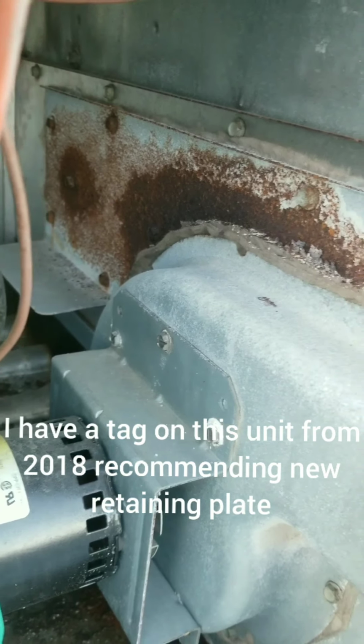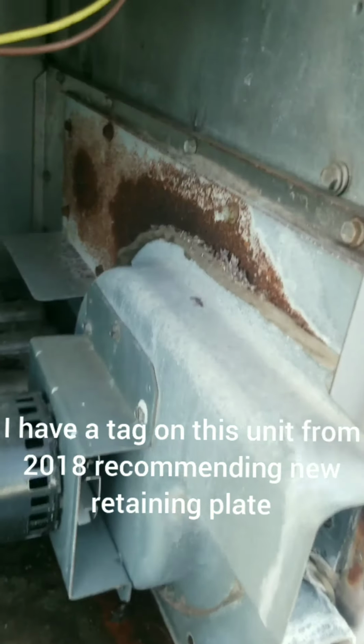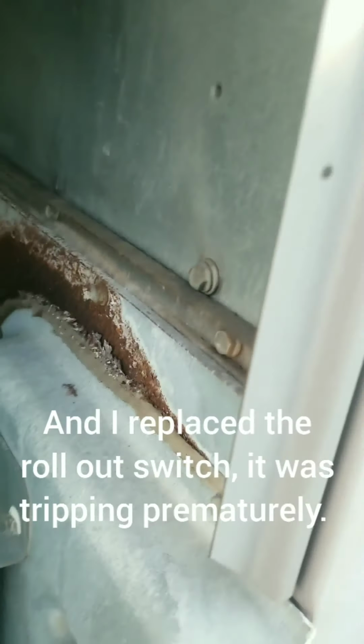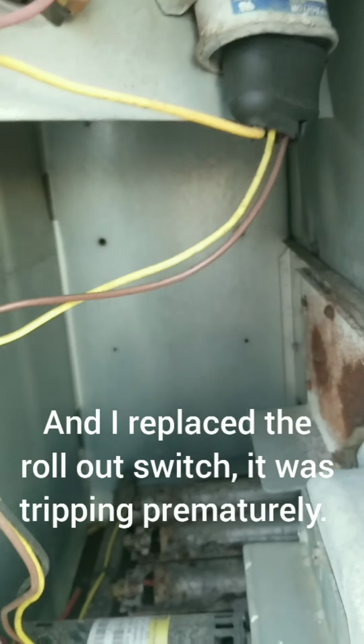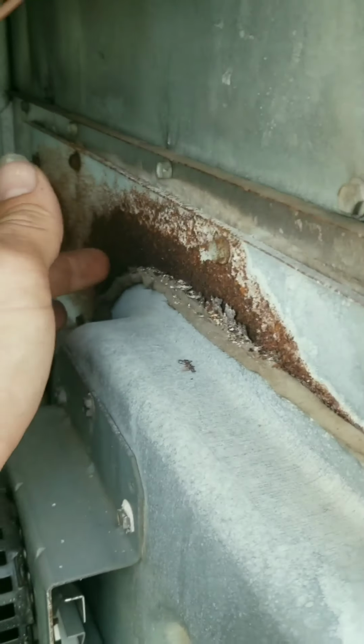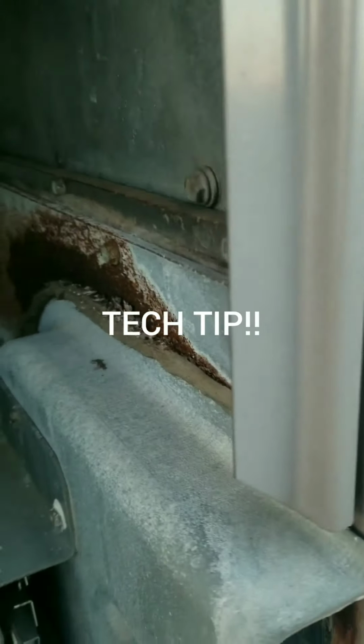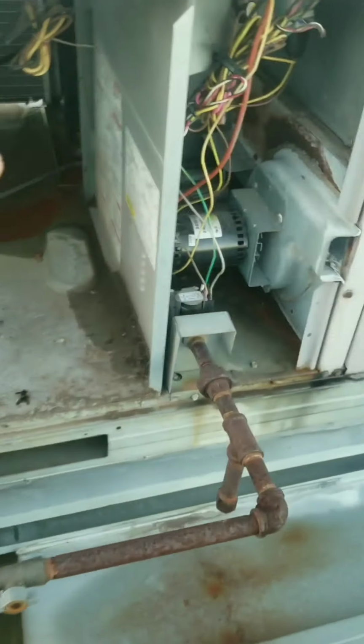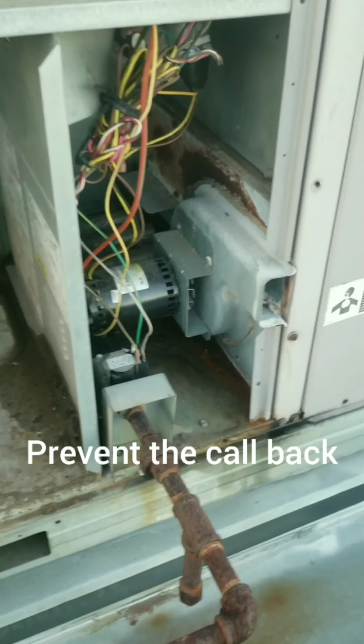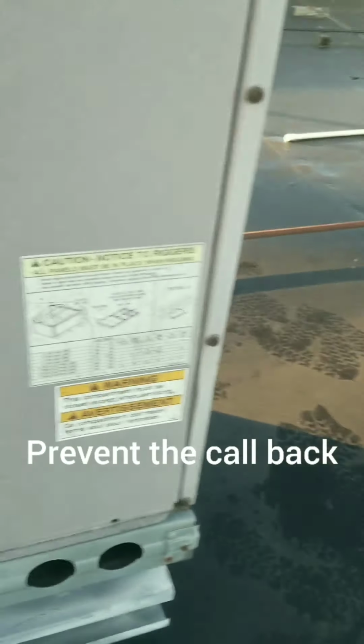Solid LED. That front retaining plate there is an issue. If the heat comes on, it heats up this section because there's nothing here to hold the heat back, and it'll actually trip this rollout switch. See it all the time. It'll actually run with this front panel off, and then as soon as you put the front panel back on, it warms up that section and trips that high limit. Let's see what we got in our blower here.